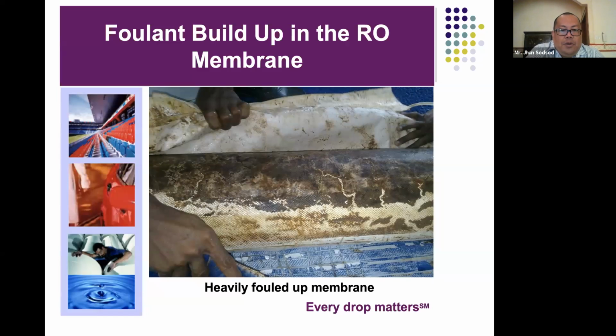So even having UF, the possibility of fouling the membrane is still there. Depending on the gravity of the situation, foulant can develop in 1 week, 2 weeks, 1 month, or 3 months, depending on the foulant carryover in the RO feed.